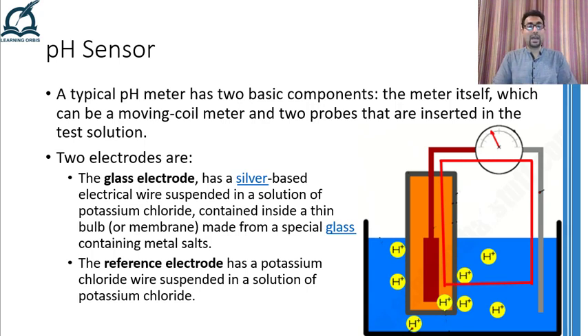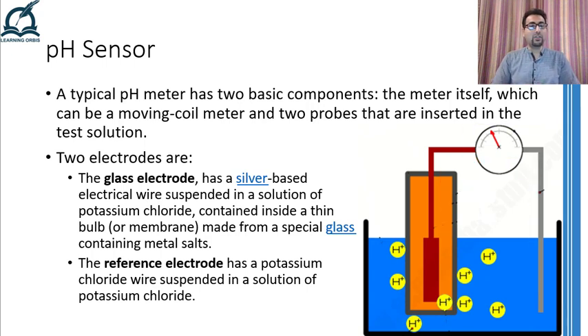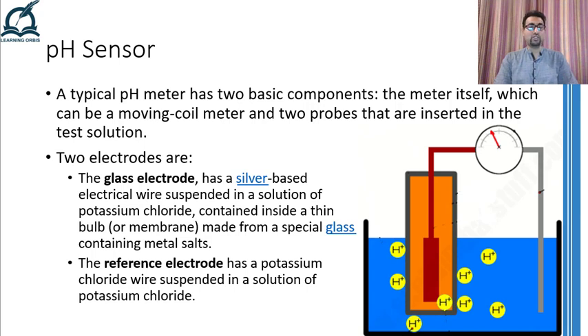This unequal ion exchange activity will generate a potential difference between the sides that will cause electrons to flow either from inside the tube to outside or from outside towards the inside of the glass tube. Hence, electron flow will start that will be measured using a galvanometer as shown in the diagram. The higher difference of ion exchange activity will indicate the strength of the acidic or alkaline solution, whereas the direction of flow of electrons will tell us the nature of the solution — that is, whether it is acidic or alkaline. The potential generated in such meters is of the order of a few millivolts, which is detected by the meter, and the meter scale shows the pH value instead of the potential difference. I hope you have understood the working of this simple pH meter that is quite widely used in industries. Thank you and take care.